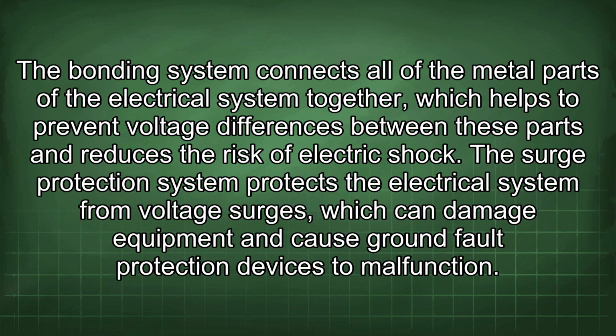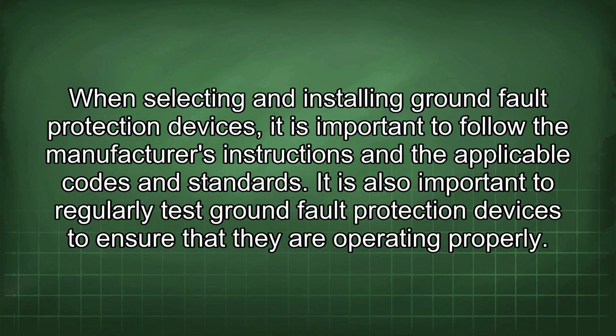The bonding system connects all of the metal parts of the electrical system together, which helps to prevent voltage differences between these parts and reduces the risk of electric shock. The surge protection system protects the electrical system from voltage surges, which can damage equipment and cause ground fault protection devices to malfunction. When selecting and installing ground fault protection devices, it is important to follow the manufacturer's instructions and the applicable codes and standards.